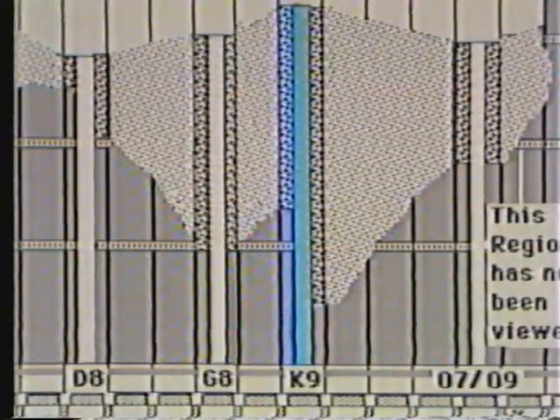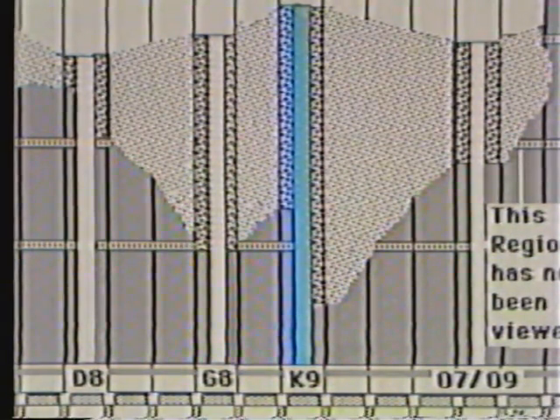In the lower core region of location K9, we find a somewhat different scene. The transition zone from intact fuel rods to a solid mass occurs at only 10 inches from the bottom of the fuel assembly. Visible in this area is small debris between the fuel rods, all the way to the bottom of the fuel assembly. The material in this area near the center of the core is not as loose as that near the periphery. At this location, the solid mass is about 5 feet thick, thicker than all other drilled positions.